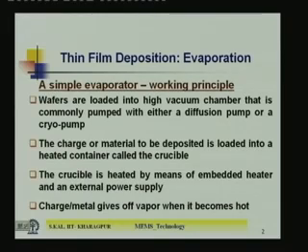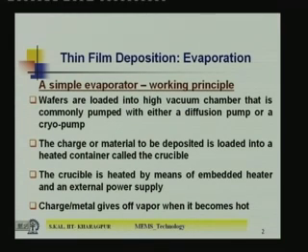In this evaporator, one vacuum chamber is used which is evacuated by certain pumps. Next, you need a crucible on which you put the material, and by applying electrical power you can evaporate the material. The material melts in the crucible, which is heated by means of an embedded heater and an external power supply. When you melt the material in the crucible, it evaporates and deposits on the wafer. This is the basic principle: create vacuum, put material on the crucible, apply electric power, the crucible becomes hot, and when the temperature exceeds the melting point of the material, it evaporates.